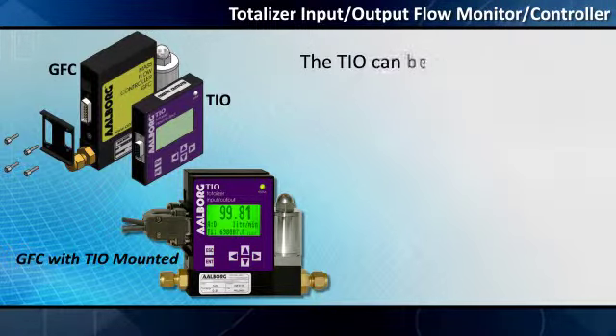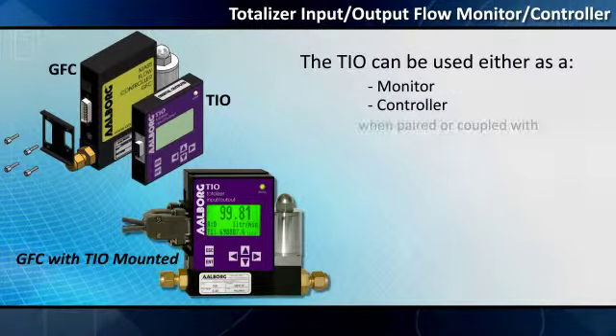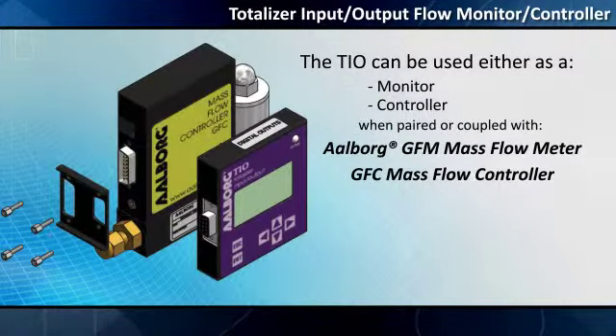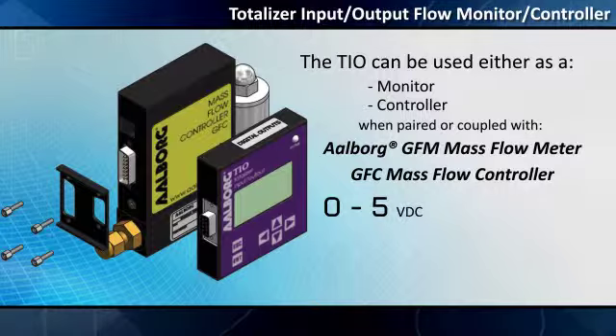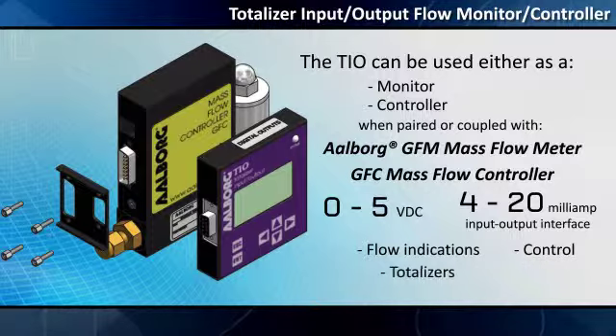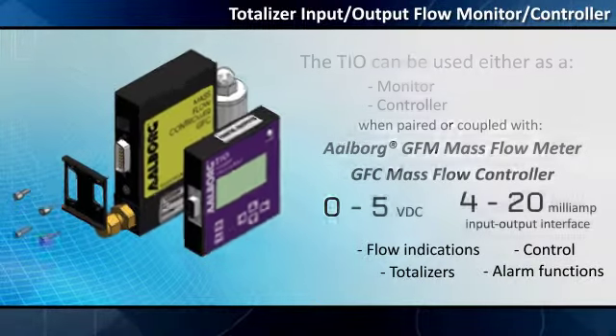The TIO can be used either as a monitor or a controller when paired with an Aalborg GFM mass flow meter or GFC mass flow controller. It is equally versatile with any third-party device equipped with a 0 to 5 VDC and/or a 4 to 20 milliamp input-output interface where flow indications, control, and totalizer or alarm functions are required.